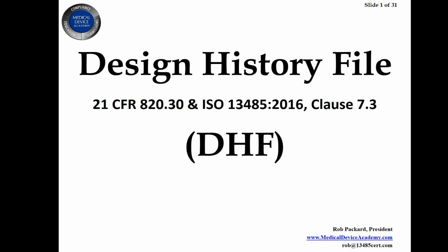And the design history file is something that's very vaguely defined by the FDA as all the records demonstrating that you followed your design plan. And that's really not helpful enough, particularly if you don't provide enough information in the FDA guidance on what you're supposed to have in your design plan either. So this is what I've created to try to help those people out.